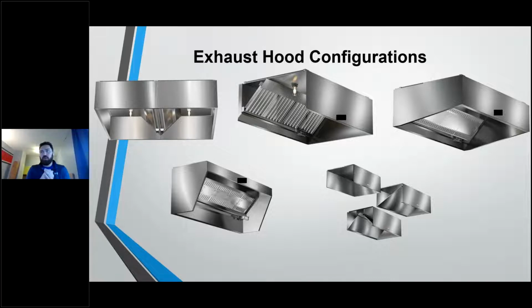One common item missed when designing this type of hood with a wall canopy and island configuration is to keep in mind that you don't have a wall at the back of this hood anymore. So you need to have a minimum of 6-inch overhang from the back of the appliances as well. That's one commonly missed item.